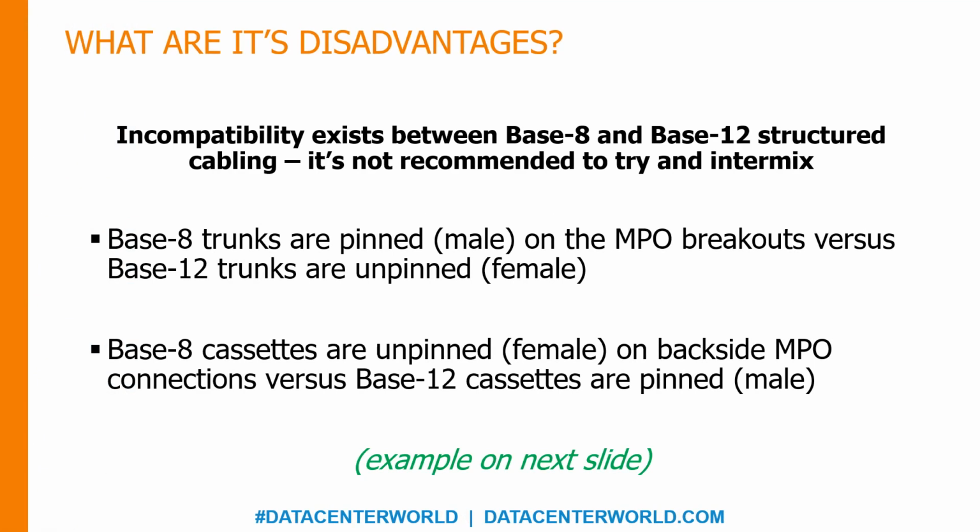There are some important differences between the trunks and cassettes in base 8 and base 12 structured cabling systems. The trunks in a base 8 system are in fact pinned. In base 12 they are not. In a base 8 system the cassettes are unpinned, and in a base 12 the cassettes are in fact pinned. Because of these differences, it's not recommended that you try to intermix base 8 and base 12 cassettes in the same computer room or environment to avoid any compatibility issues.